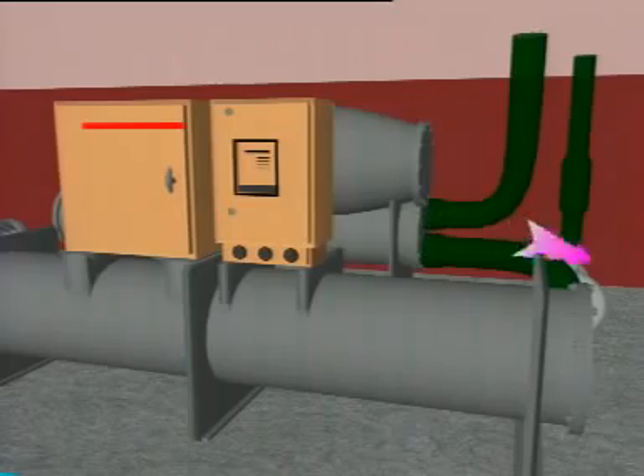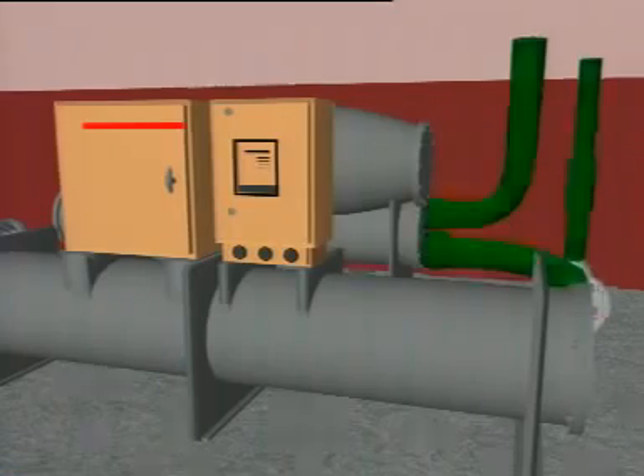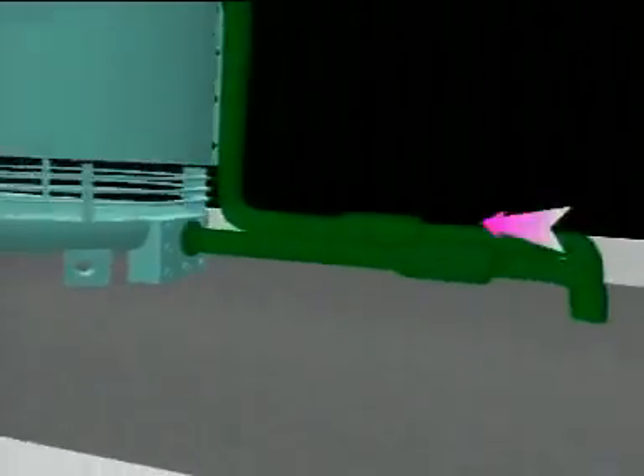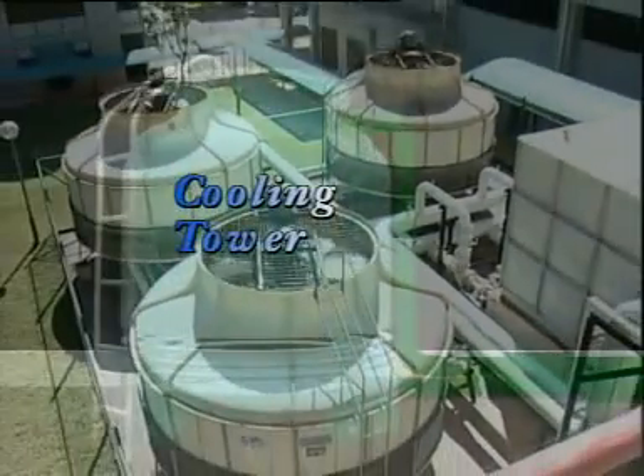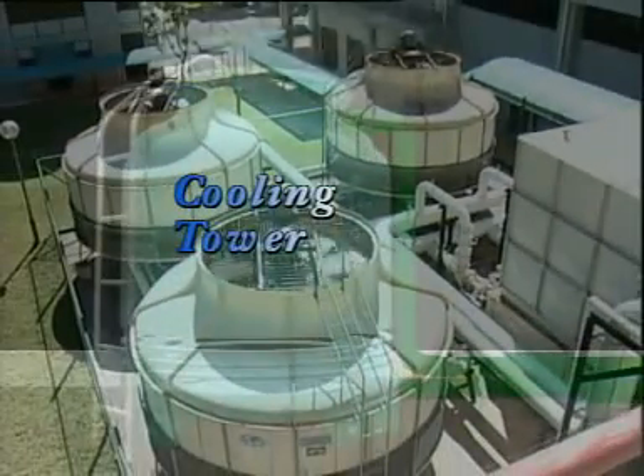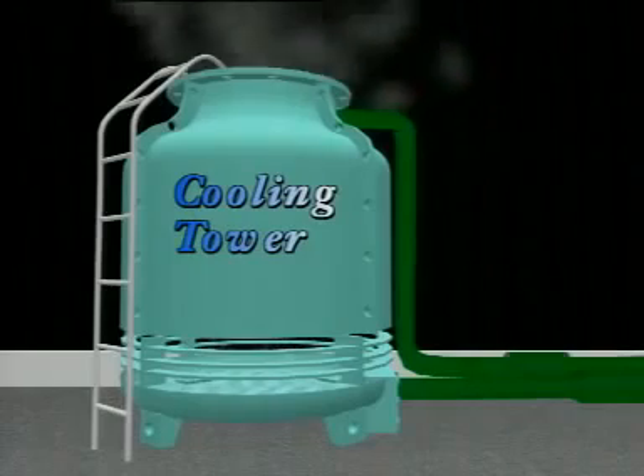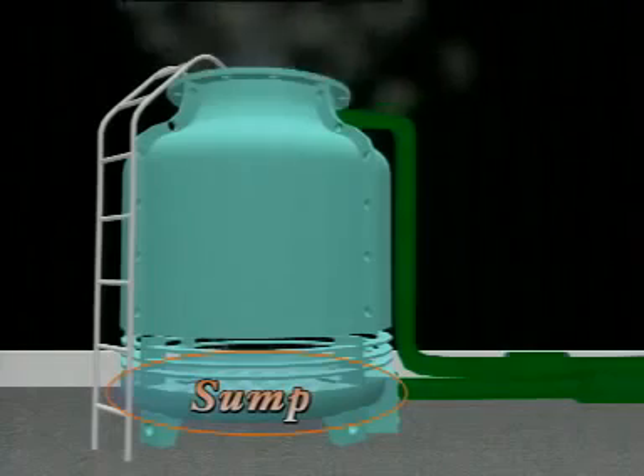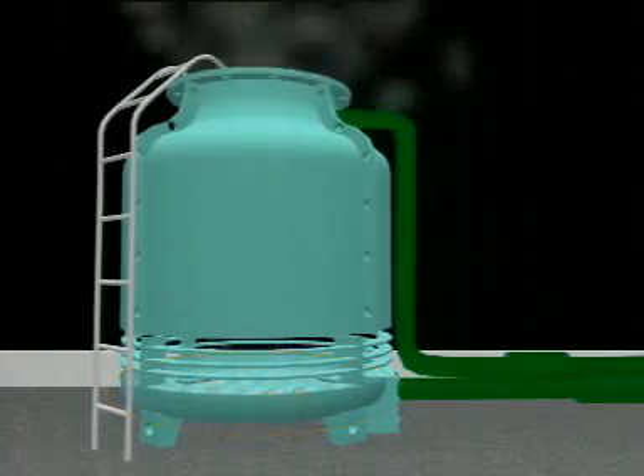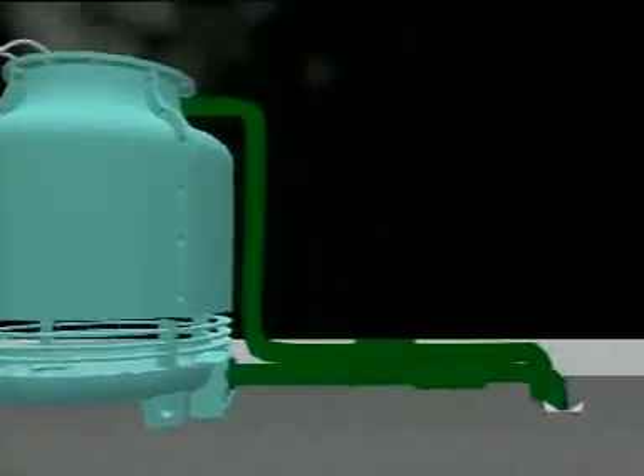The condenser water is then pumped to the cooling tower, which is located outdoors. The heat absorbed by the condenser water is rejected to the outside air. The 29 degrees Celsius condenser water collects in the sump of the cooling tower. It then flows back to the condenser of the chiller to again absorb heat, and the cycle repeats.